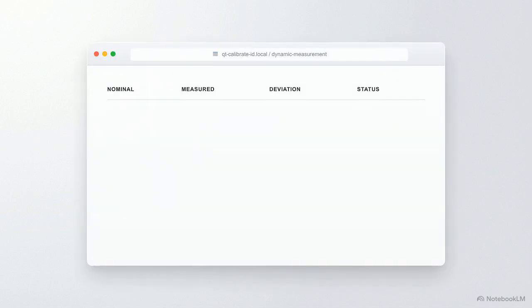In Step 2, the technician enters their calibration data. As they input the nominal and measured points, the browser automatically calculates the deviation. It then dictates a simple pass or fail status based on the pre-programmed tolerances.